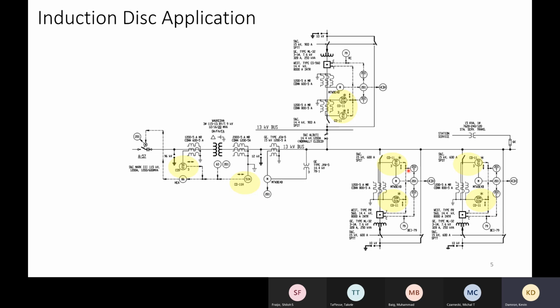Then we've got our feeders. Then we've got CO11s. Again, 3 of them, 1 per phase, and 1 on the neutral. And then if any of those operate, they come down and hit the trip coil for a breaker. So now, interesting thing is if you start counting these up, there's 3, 4, 7, 8, 12, 16 relays in the substation that are electromechanical relays.